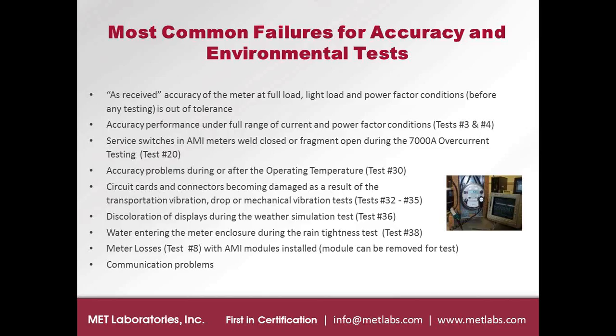There's actually also an additional technical requirement, C12 TR30, that has some additional focus on the service switches as well that could be run, although it's not necessarily part of C12.20 or 12.1. But it could be a situation where your buyer would request those types of tests be run as well. Operating temperature, talked about that, particularly at the extremes. The vibration, the mechanical or the transportation vibration and drop in particular could be an issue.